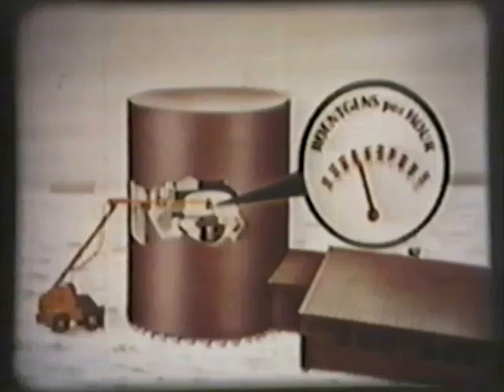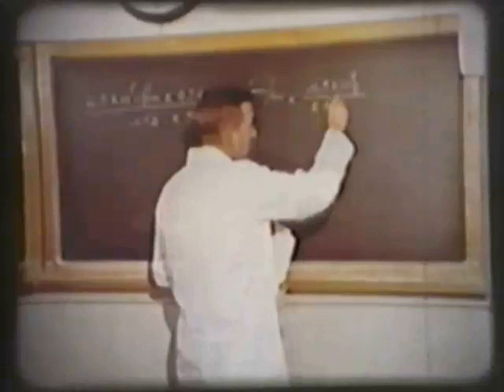First estimates of the radiation field in the reactor room were calculated to be approximately 1,000 R per hour. By late April, the radiation levels had decreased to the 200 R per hour range. Films from a pinhole camera spotted several locations and sources of high gamma radiation activity outside the reactor vessel, presumably from reactor components blown from the core by the force of the explosion. Calculations of the energy needed to cause the observed damage to the ceiling and the reactor indicate that the explosion was sufficient to create an internal pressure of 500 psi.